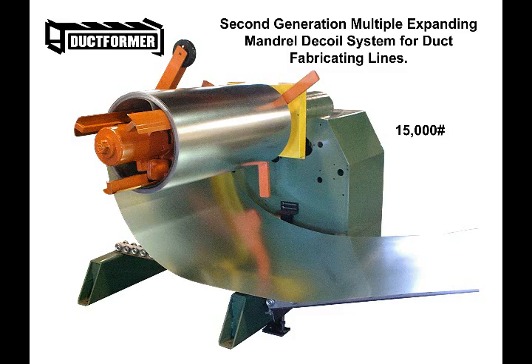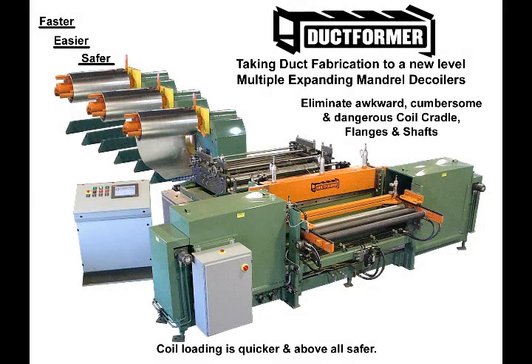The Ductformer multiple expanding mandrel decoiler system is a very cost-justifiable upgrade and can be adapted to any coil-fed duct fabrication line. The system consists of one to six in-line and under-fed 15,000-pound expanding mandrels. Each station has an independently actuated loop control payoff with a pneumatic backup feed roll to assist in feeding and rewinding the coil strip.